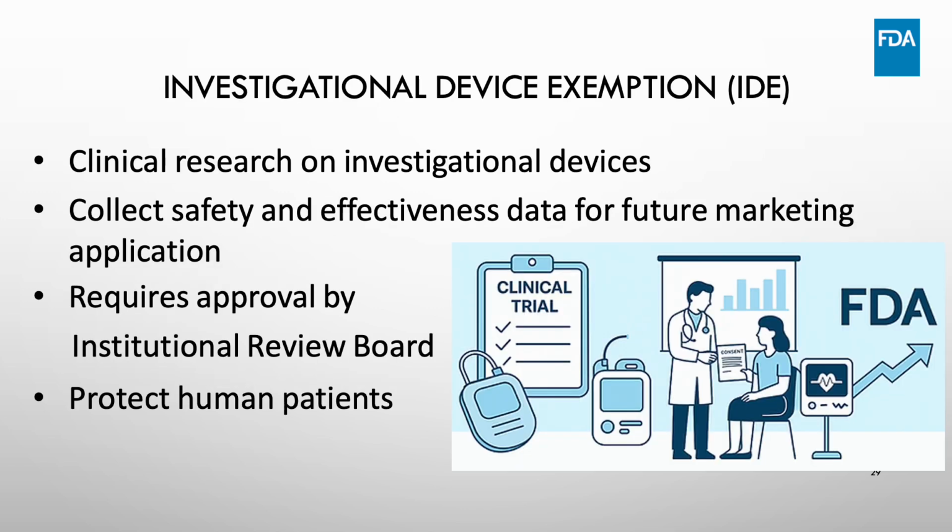Let's start with the investigational device exemptions, or IDE. Of the five we will review, this is the one submission when you are not asking to get your product to market. Instead, this is the submission when you're asking for FDA approval to conduct clinical research on your investigational device. In an IDE, you are collecting clinical safety and effectiveness evidence as part of your overall valid scientific evidence that you plan to include in a future marketing application.